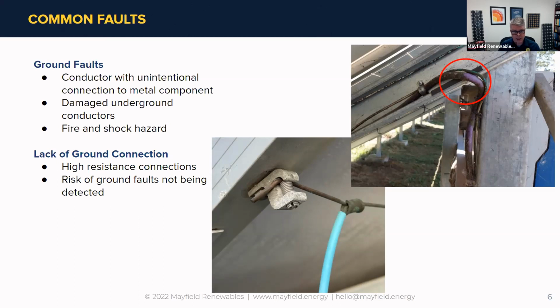The issue and the problem is, I've seen this time and time again: those lugs, maybe they didn't use the right outdoor rated lug, or they didn't make that connection the right way. So there's a legitimate and real risk that we don't have a good connection to ground, that the lug has corroded, and we don't have a great ground connection. That's something we'll talk about testing for.